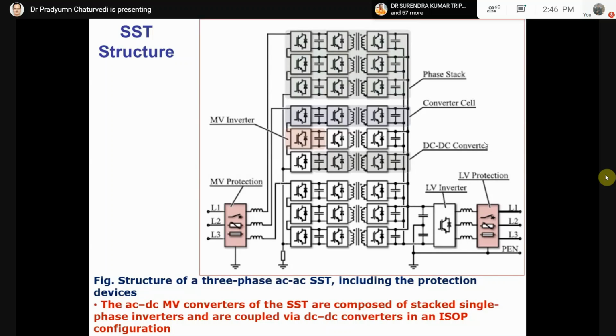This is the beauty of this structure, and it depends on how many stacks or modules you use per phase, depending on the rating, current, voltage and power rating of the system. So this is the phase stack, converter cell, DC-DC converter, and protection at LV and MV side, everything inside this. You can have flexibility where every output is given to a separate AC, or you connect them in input series output parallel, or input parallel output series, depending on voltage and current requirements of the load side and available rating at the source side.